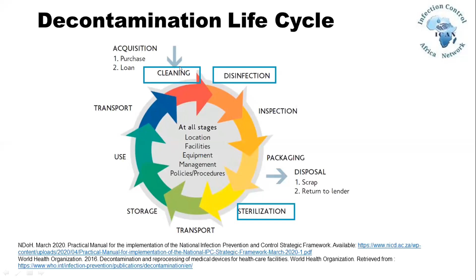So the general principles are that single-use items should never be reprocessed. All reusable medical devices must be processed in a decontamination area. No cleaning or packaging of medical devices should take place in a clinical area. Medical devices should be rinsed off to remove gross soiling at point of use. That's a very important point, okay? Try and rinse it off where you have used it. Medical devices should be transported safely to the area of decontamination. And your decontamination units, your CSSD, must have separate dirty and clean areas for reprocessing, and proper ventilation. Your staff must also work in either the dirty area or the clean area.